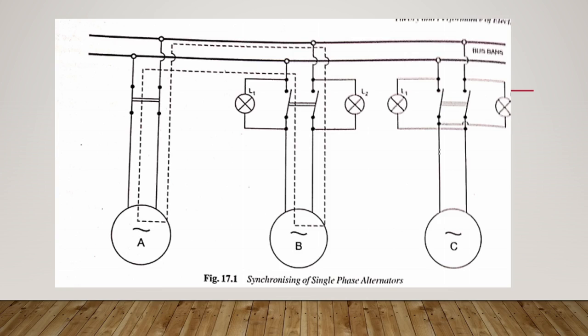Before connecting an alternator to the bus bar or in parallel with another alternator, three conditions, which we already discussed, must be satisfied. The terminal voltage of the incoming machine must be exactly equal to that of the others. The speed of the incoming machine must be such that its frequency equals the busbar frequency. And third, the phase of the incoming machine voltage must be the same as that of the busbar voltage, that is, the phase voltages of the incoming machine and the bus bar should be in phase. These three conditions must be satisfied before we synchronize the single phase alternators.